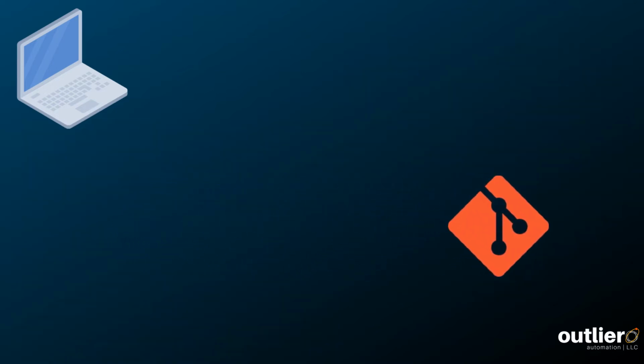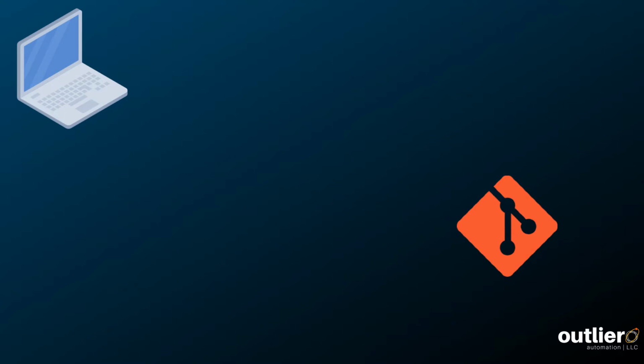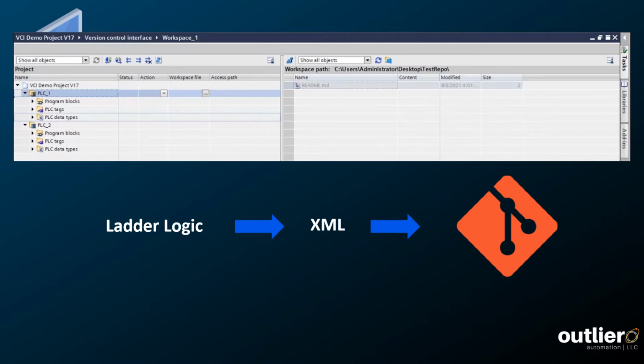Now, to use Git to track PLC project files, you need a way to convert the graphical programming files to a text-based file and then transfer it to Git. This is where Siemens TIA Portal Version Control Interface comes in. Just like it sounds, VCI is TIA Portal's interface to Git. It can export or import program blocks, which allows us to do backups, archiving, rollbacks, and share code between team members.